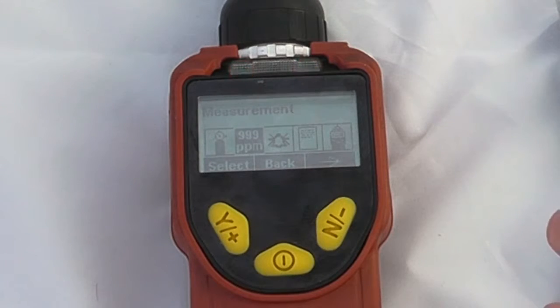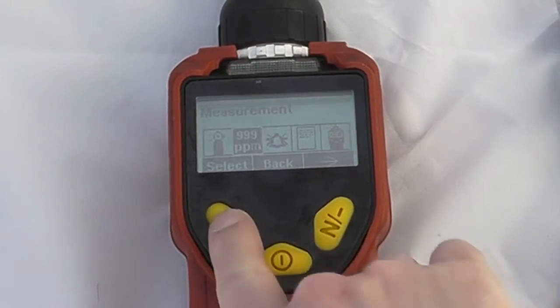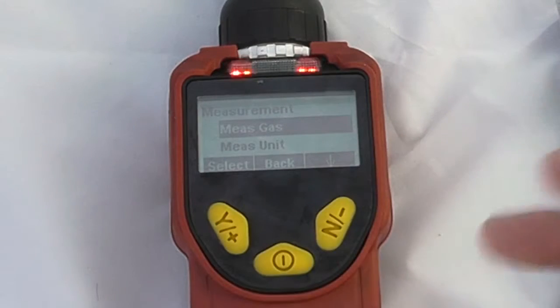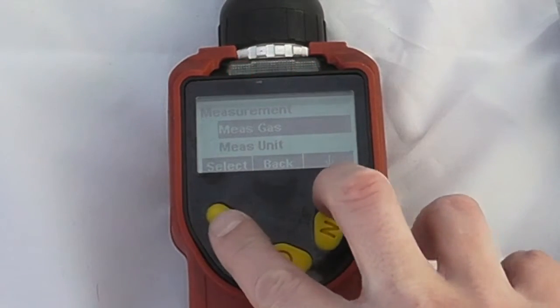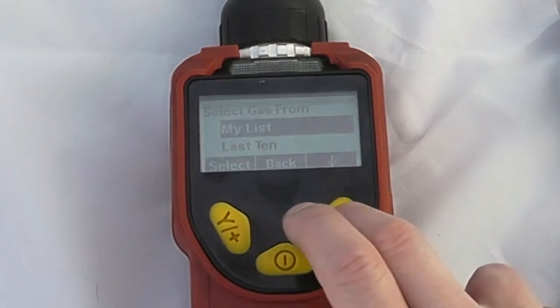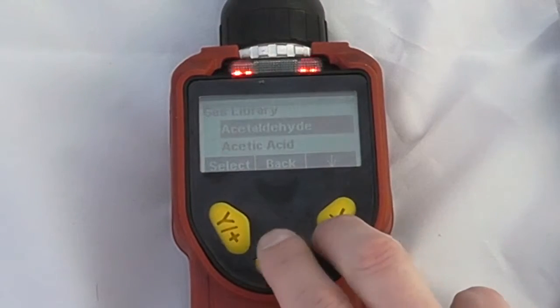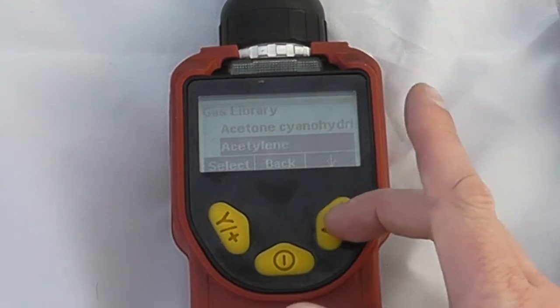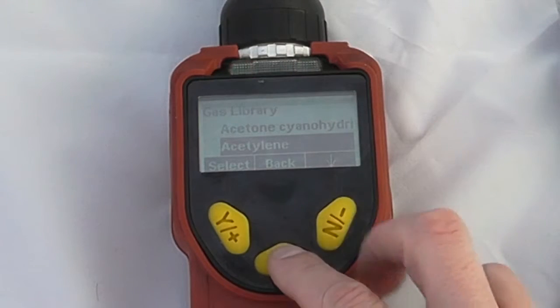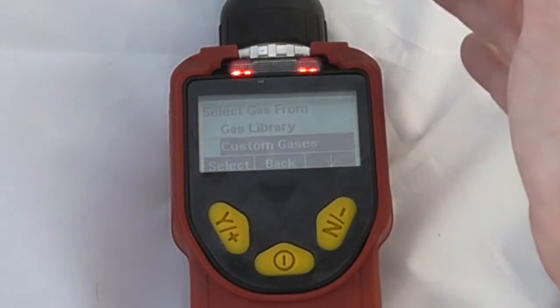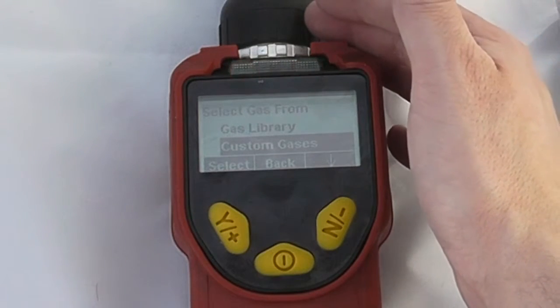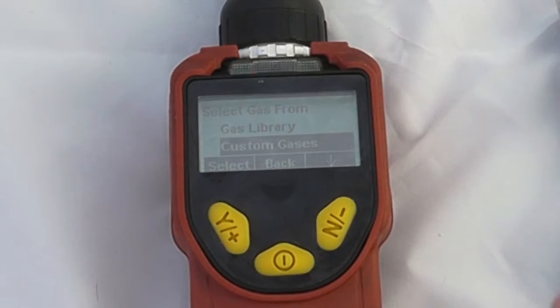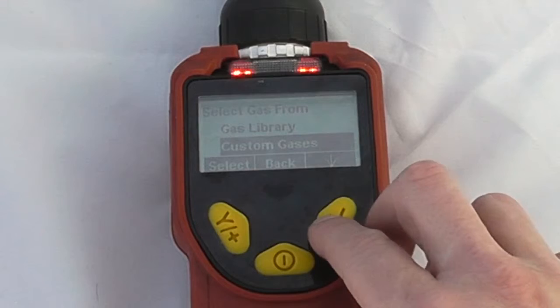Our measurement options include our measurement gas, be it benzene, isobutylene or other. We can select from a list from the last 10 used or from the gas library. Again, this has all the standard correction factors applied as you would find with any VOC monitor. The thing to bear in mind with this instrument is it functions with a 9.8 electron volt lamp, not the standard 10.6 electron volt lamp, so there will be some gases that are unionizable with the UltraRAE instrument that would be available in the Mini RAE instrument.